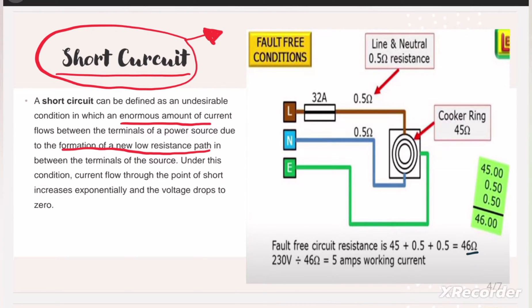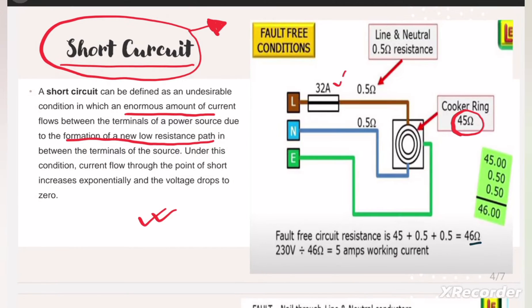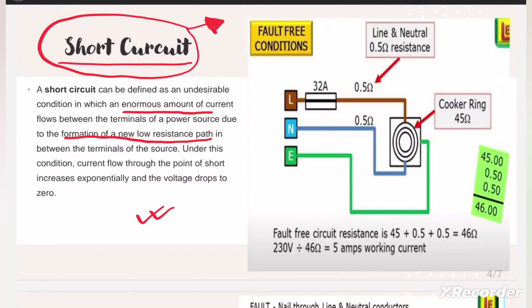To understand short circuit, let us consider a healthy circuit first and then create a short circuit condition. Here I have a healthy circuit with an electrical cooker having a resistance of 45 ohms. The wire resistance is 0.5 ohm for the phase wire and 0.5 ohm for the neutral wire, and there is a circuit breaker rated at 32 amperes. Current flows from the line through the cooker and back to the neutral. The total resistance of this path is 0.5 + 45 + 0.5 = 46 ohms.